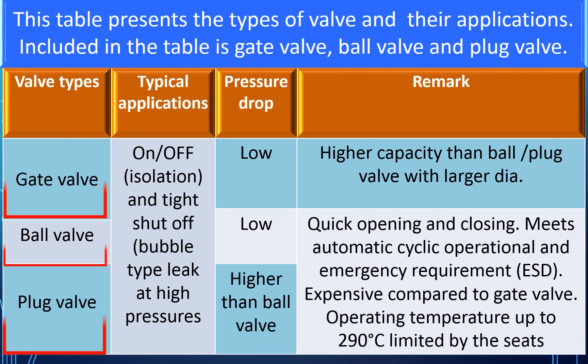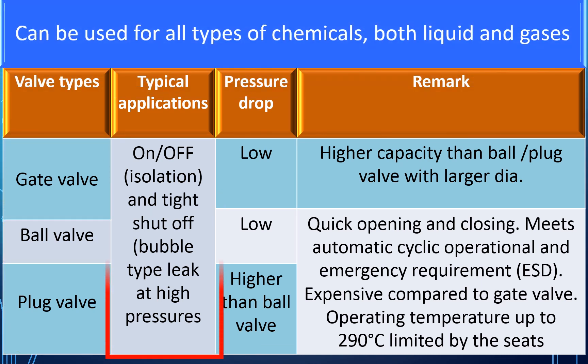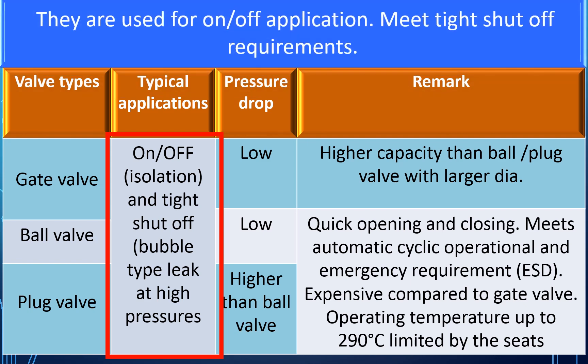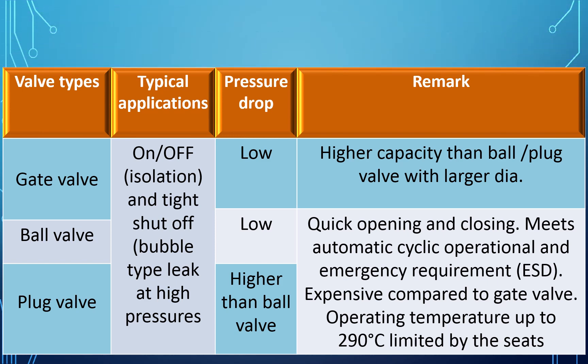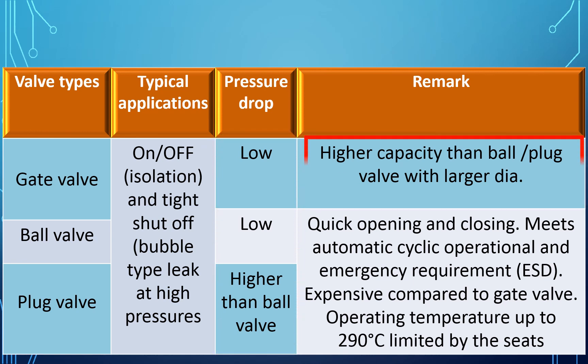This table presents the types of valves and their applications. Gate valve, ball valve, and plug valve can be used for all types of chemicals, liquids, and gases, and are used for on-off applications. They meet tight shutoff requirements. At high pressures, these valves will have bubble-tight leak performance. Gate and ball valves have low pressure drop, while plug valves have higher pressure drop than ball valves. Gate valves have higher capacity than ball valves and plug valves.